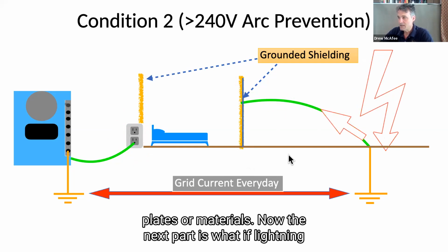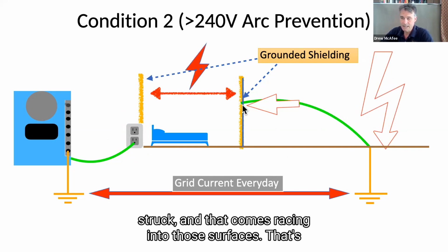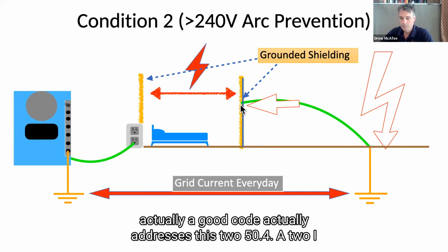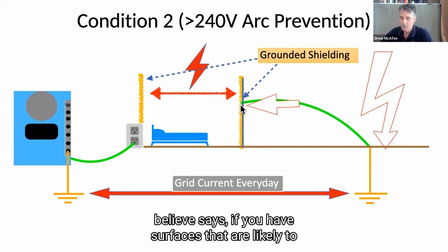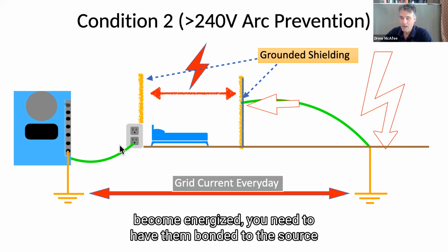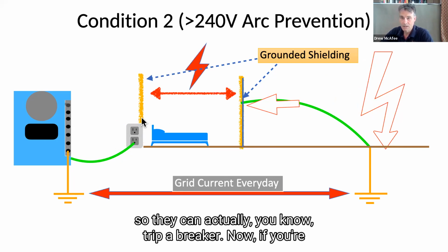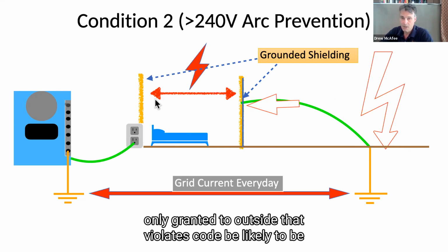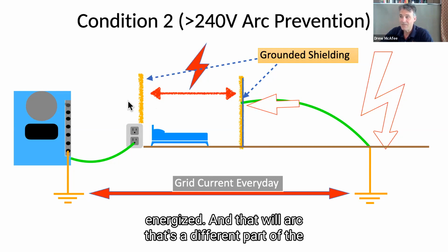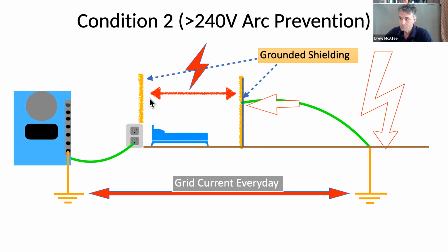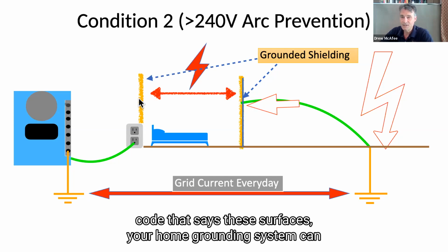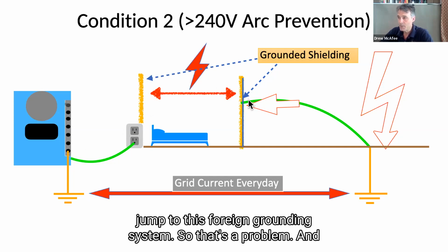Now, what if lightning struck and that current comes racing into those surfaces? The code actually addresses this—250.4A2, I believe—which says if you have surfaces likely to become energized, they need to be bonded to the source so they can trip a breaker. If you're only grounded to outside, that violates code, because surfaces likely to be energized will arc. A different part of the code says your home grounding system can jump to this foreign grounding system, so that's a problem.